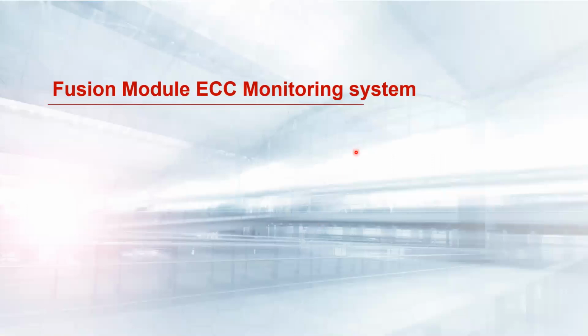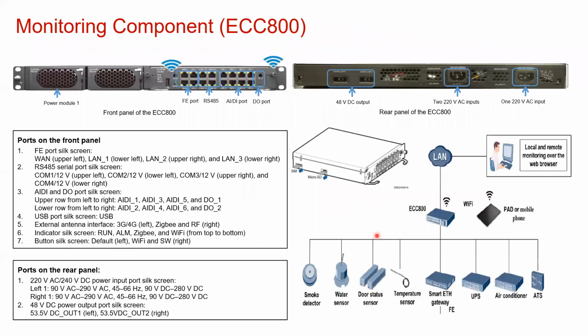So now I'm moving to the monitoring subsystem. This monitoring subsystem is called ECC, and on this ECC, you can see the various inputs are there, and all your sensors are talking to this device. There we have multiple layers of connections. We can say the device input output ports, or the Ethernet ports, for making the SNMP integration. Even this device can integrate further for upper layer monitoring in the NOC center. Maybe somebody in the NOC area has their own tool. So ECC can further be integrated over SNMP with the monitoring system, or the operator can directly log into the ECC web portal and see all this device monitoring.